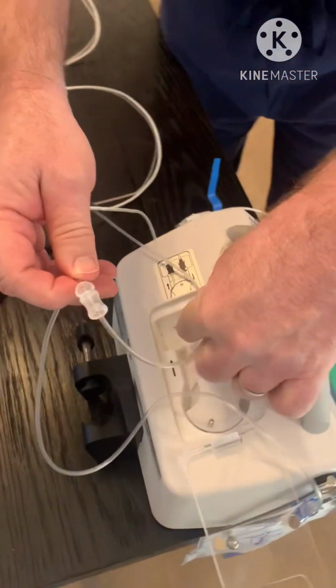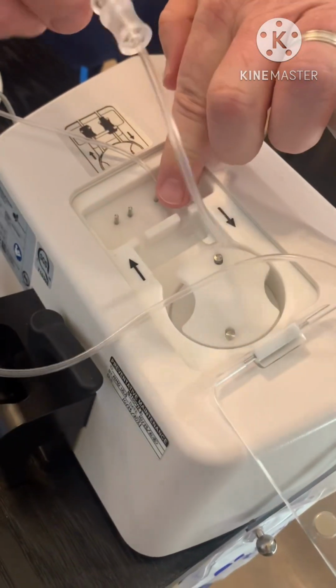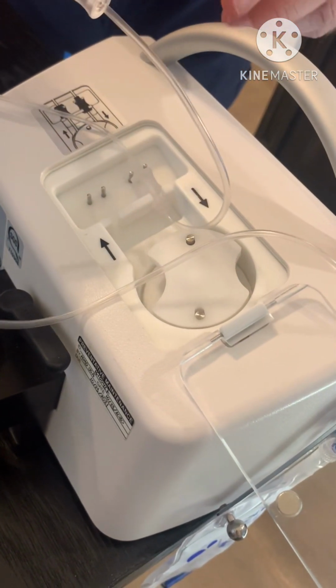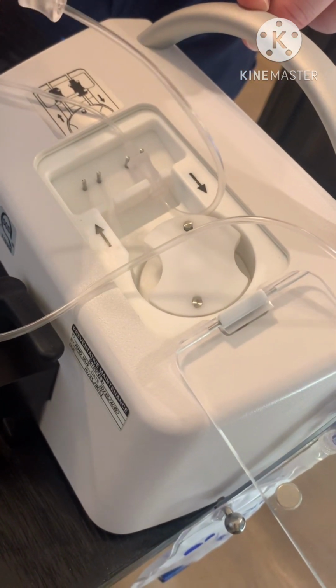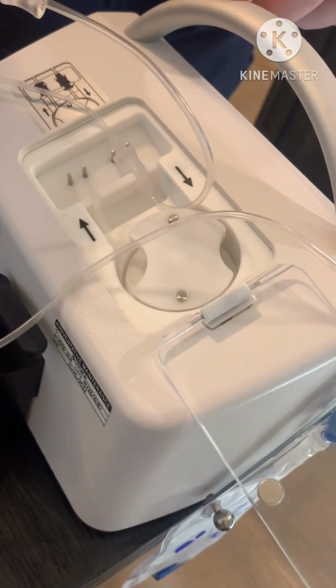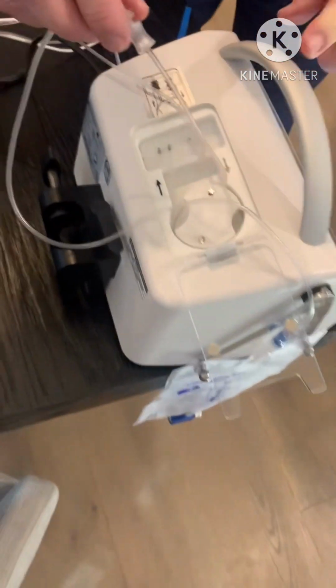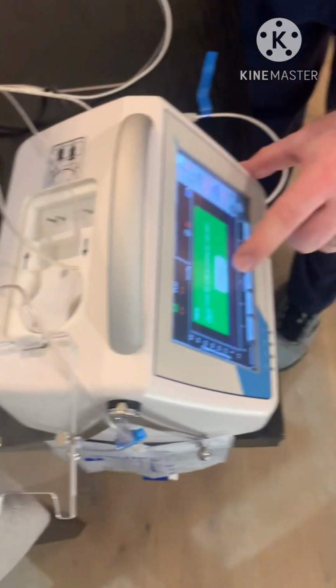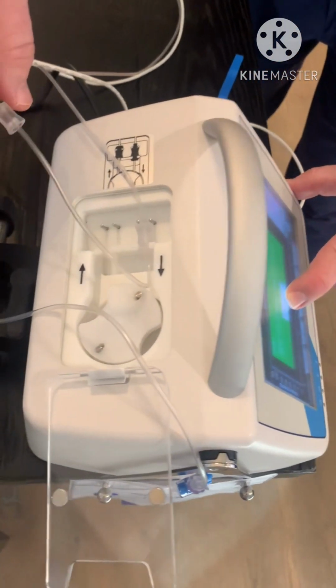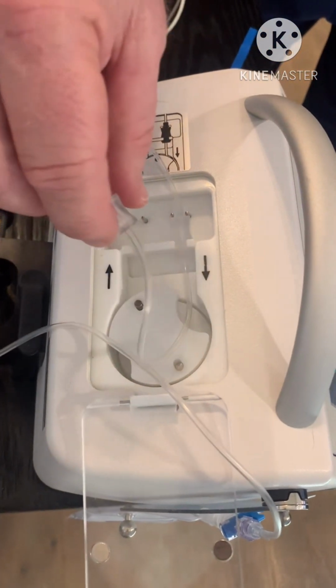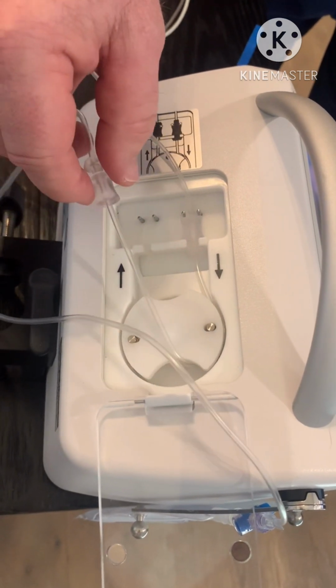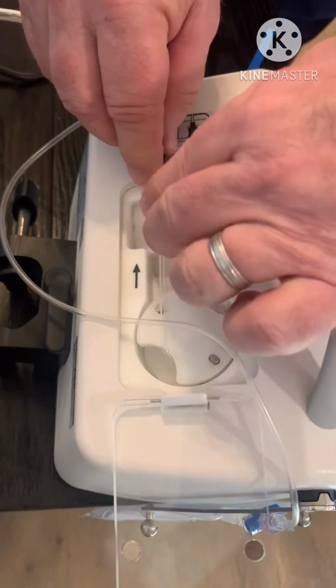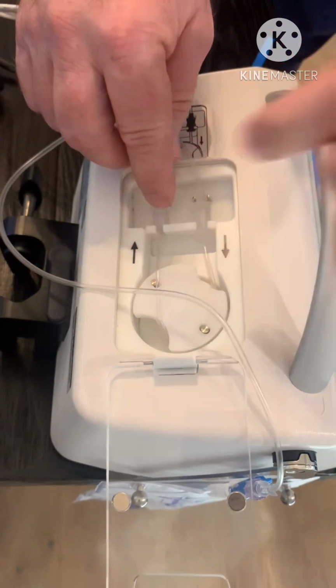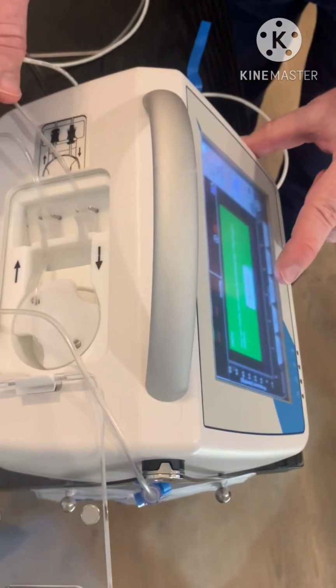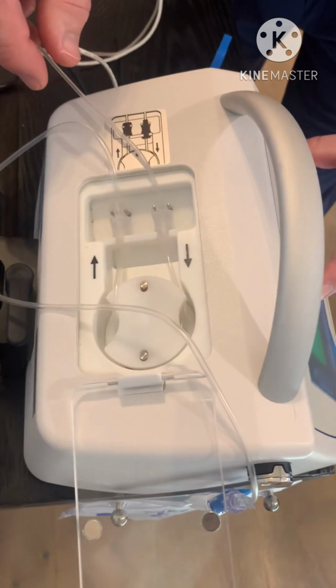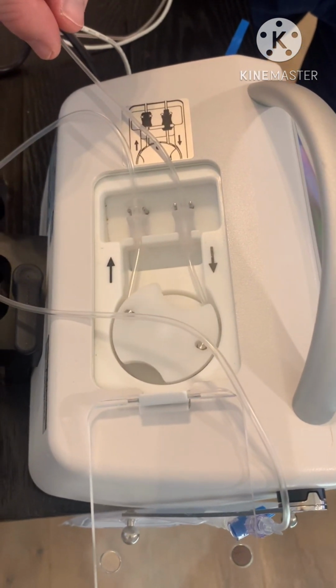When you lift the lid while loading, you're going to see a turn rotor sign. So you gently load your tab with the tail, and let the machine do all of the work, because if you force this or try to muscle it, you risk possible damage to the tube set. This is sensitive equipment. Once that tab is in, you go back to the turn rotor button, hold it down, and let the tube find the half moon and load itself. Once it's about halfway through loading, load your bottom tab, go back to the turn rotor button, hit that, and hold it down until the tube set is finally loaded.